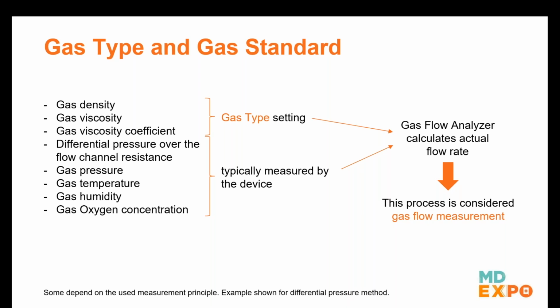But if you had it set to 100% oxygen, you're measuring air only. Is there a calculation to figure out how far off you are? There is, yes. Off the top of my head, I don't know it, right? What percentage it is, but yes, there is a calculation that tells you, yeah, you're off by X number because you're measuring the wrong gas. Yeah, it's fairly significant. Things like temperature are more significant. So all these different conditions of the gas that we talk about, along with its characteristics, some influence more than others how much volume changes, okay?